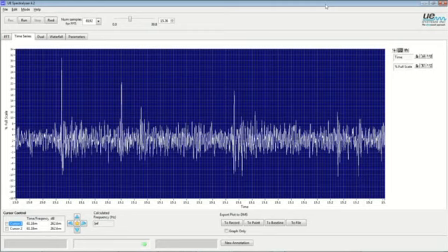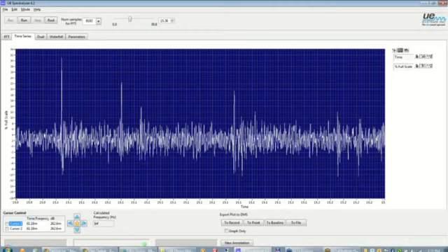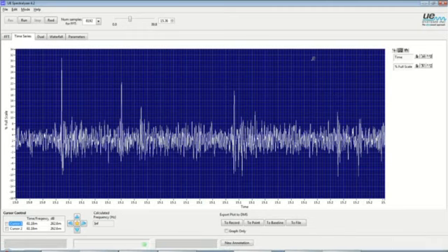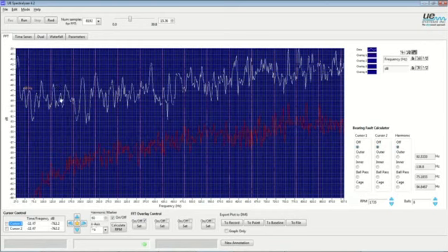So summarizing that for this particular event, when I see on the frequency analyzer, going back to this, I'm looking for certain 60 hertz peaks. There's no good way to say how many, but a 60 hertz system will have some peaks with an abundance of frequency noise in between each of the harmonics throughout the spectrum. That tells me it is electrical in nature.